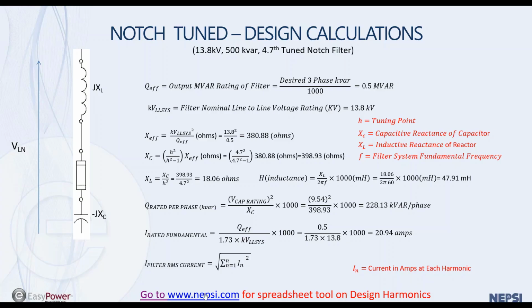On our website at www.nepsi.com, we have some spreadsheet tools for designing harmonic filters, and there are three major types of harmonic filters used. There's high pass, C high pass, and there's notch filter. We have a spreadsheet tool that is made available to consultants, whoever would want to use those. They help to evaluate the values of X of C, or the value of the capacitor in a reactor, and come up with the correct design parameters based upon tuning point. So I would suggest that you consider going there. It's under the resource page on our website.